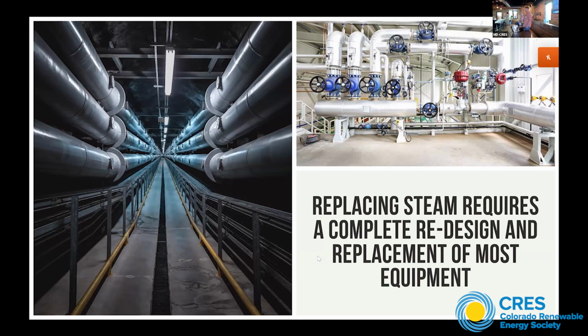Steam is an incredibly energy dense medium. We can take steam, put it through a heat exchanger, and a very small volume will create a tremendous amount of heat. If we switch to hot water instead, we need a lot more volume, which means replacing the heat exchangers, the piping, the boilers—basically everything that touches the steam. That's a tremendous amount of capital investment. So my thought is: how do we decarbonize the steam itself instead of throwing out the whole system?